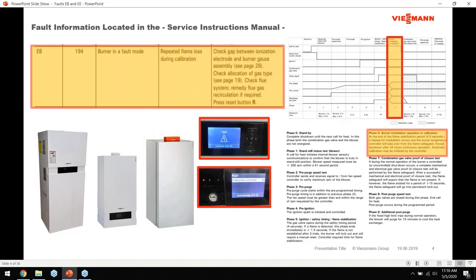Moving into EB - it's a similar type of fault related to the ignition process. The boiler fires, but we continually have repeated flame loss during calibration. This occurs in phase six: the burner is lit, the boiler is operating, and we're losing that flame signal. There needs to be a particular time period for the calibration process to complete, and this is where the flame drops out before completing. It cycles similar to an EE fault, giving the burner multiple opportunities to complete calibration, and if it doesn't, that's when you get the EB fault.